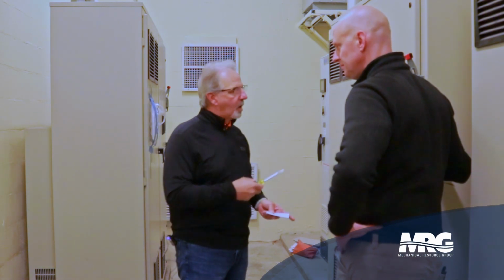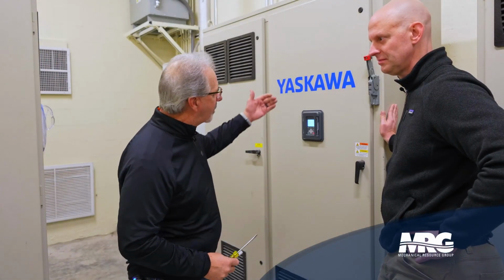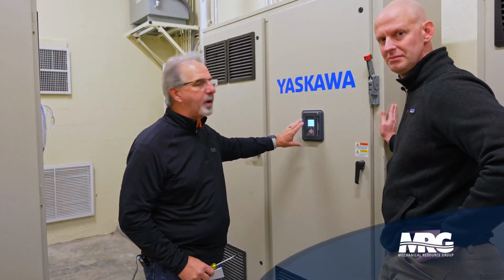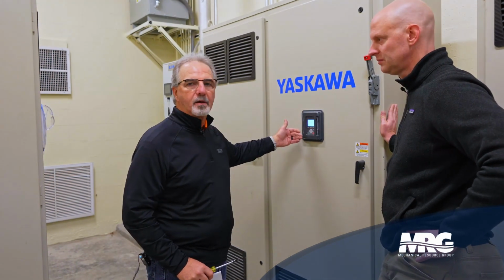This drive here is based more on a constant torque output, just simply because of the amount of head that we need to create on these pumps. Yeah. So I'm going to go ahead and swing the door open. Here on the front is the keypad where any operator will actuate. He can collect all the data.